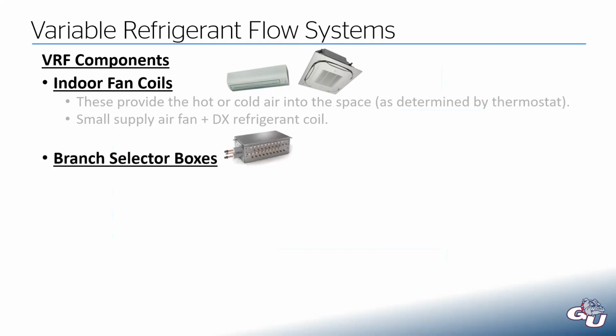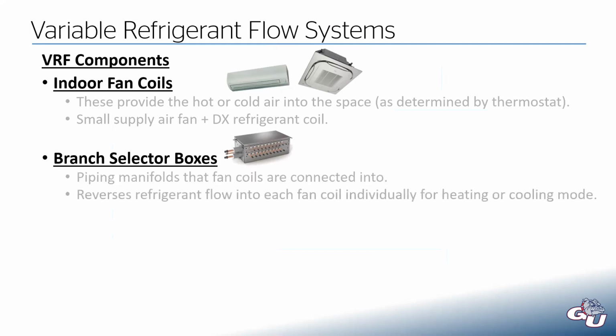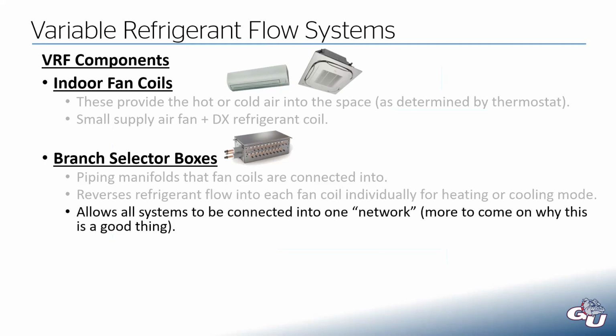The branch selectors are basically a piping manifold. So all of the fan coils connected to that box, it basically is just a bunch of spaghetti coming out of that thing and going out to the fan coils. And this is the primary device that's going to change the refrigerant flow direction depending on what those fan coils want, and allows all these units to be connected into one network. And I'll explain why that's a great thing here coming up.